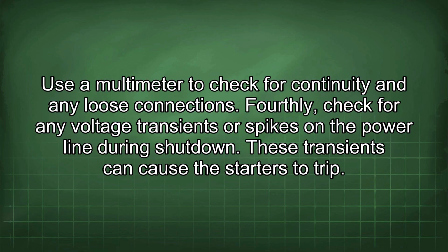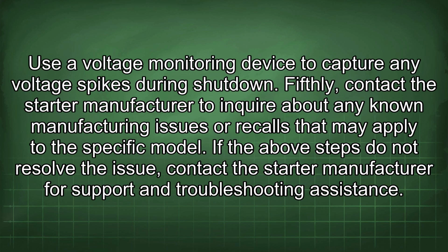Fourthly, check for any voltage transients or spikes in the power line during shutdown. These transients can cause the starters to trip. Use a voltage monitoring device to capture any voltage spikes during shutdown. Fifthly, contact the starter manufacturer to inquire about any known manufacturing issues or recalls that may apply to the specific model. If the above steps do not resolve the issue, contact the starter manufacturer for support and troubleshooting assistance.